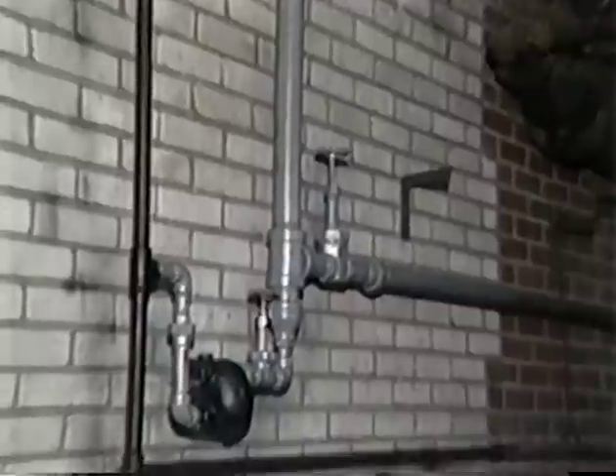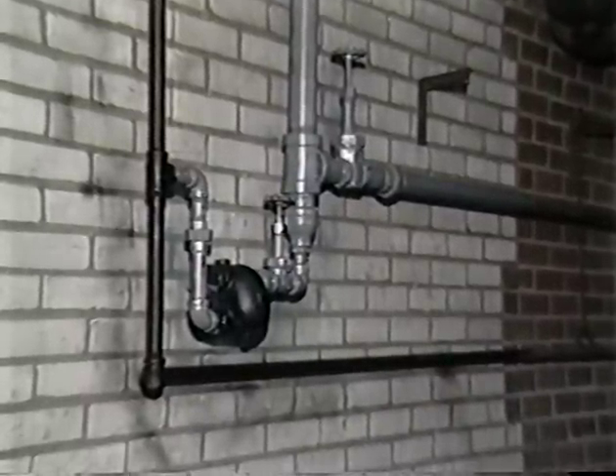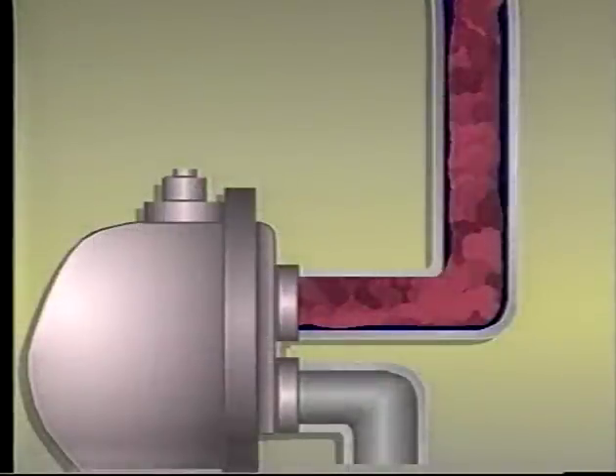Differential shock can also become a problem when elevated heat exchange equipment is drained with a substantial vertical drop ahead of the trap. Under normal conditions, condensate drains down the walls of the pipe.